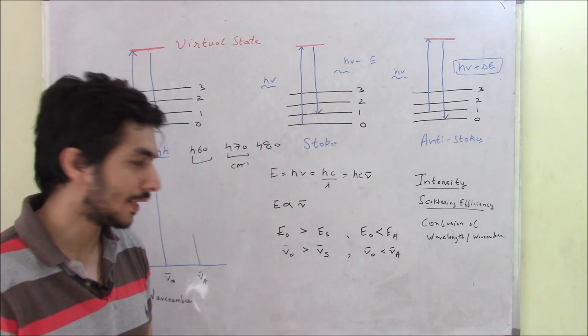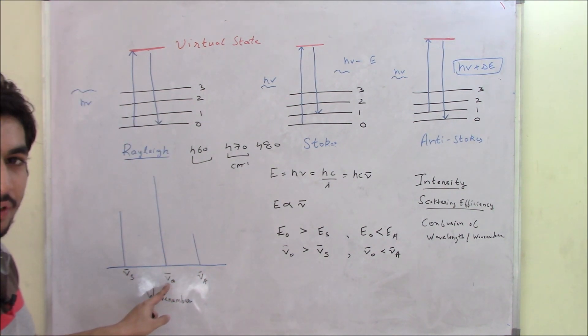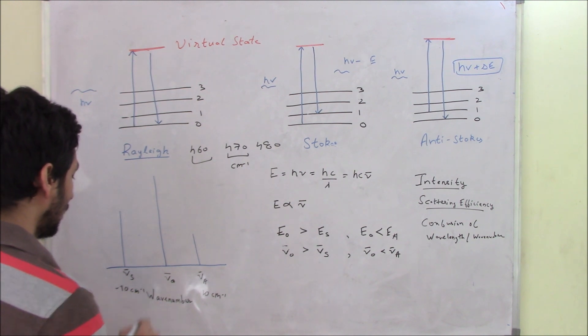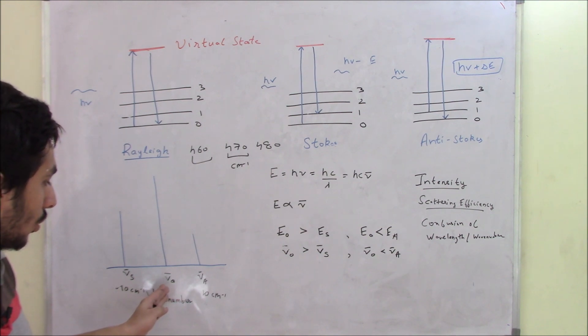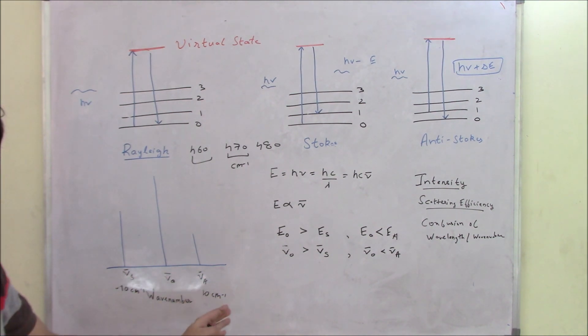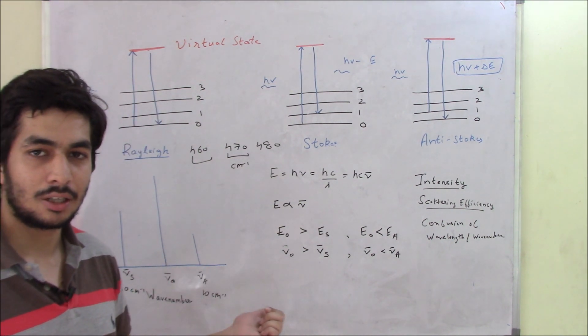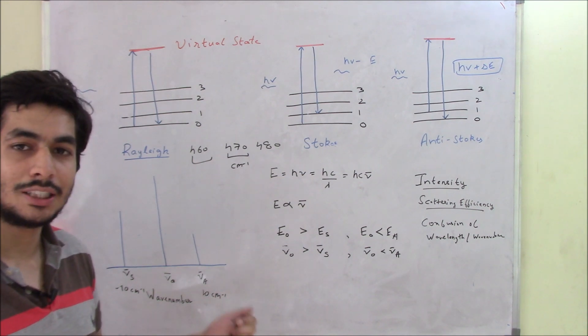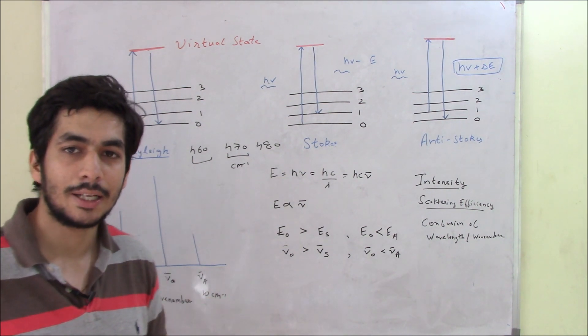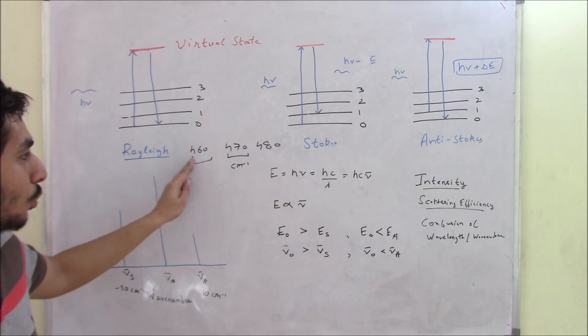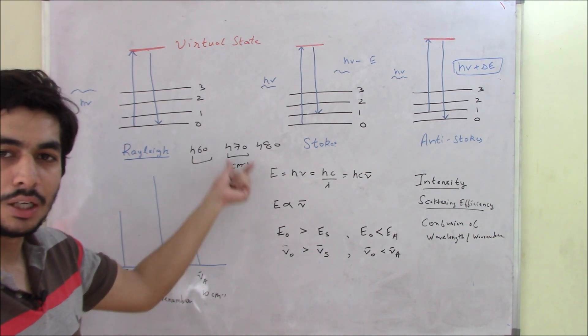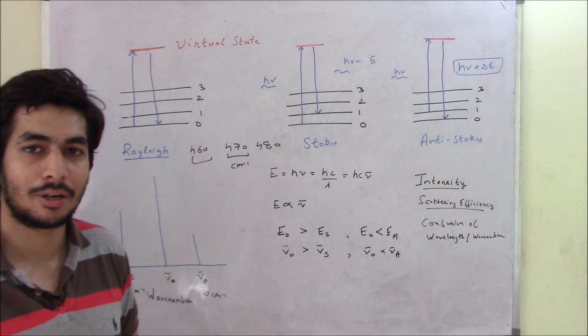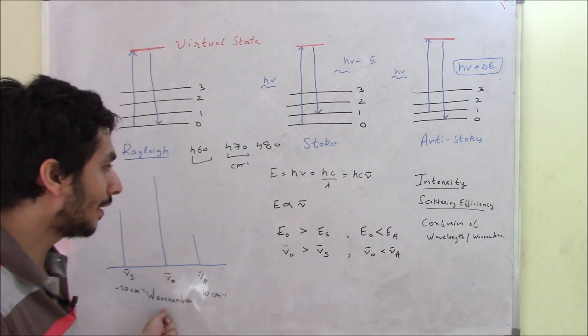This is a reference convention. For example, if the Rayleigh photon has a wave number of 470 cm⁻¹, then 460 cm⁻¹ is the Stokes wave number and 480 cm⁻¹ is the Anti-Stokes wave number. We take V₀ as zero reference, so 480 becomes +10 cm⁻¹ and 460 becomes −10 cm⁻¹. That is why in Raman spectrometers you see negative and positive signs: positive represents Anti-Stokes and negative represents Stokes.